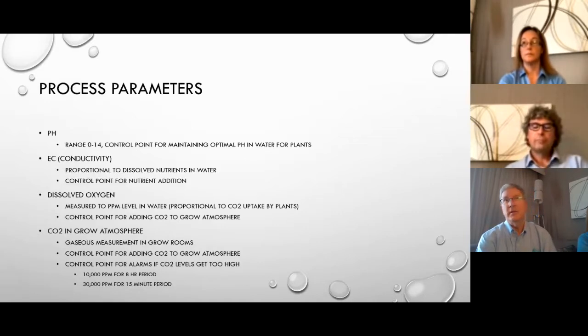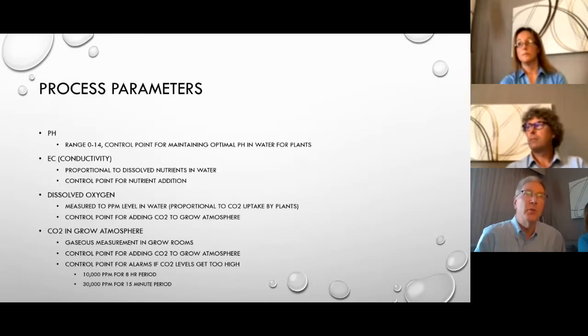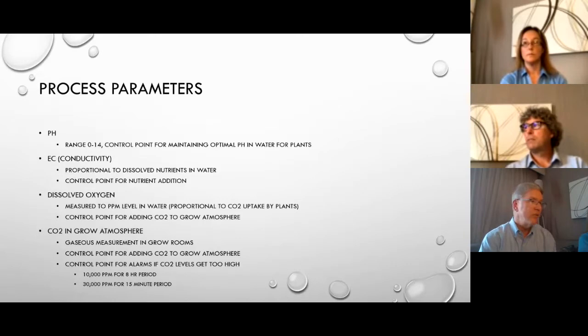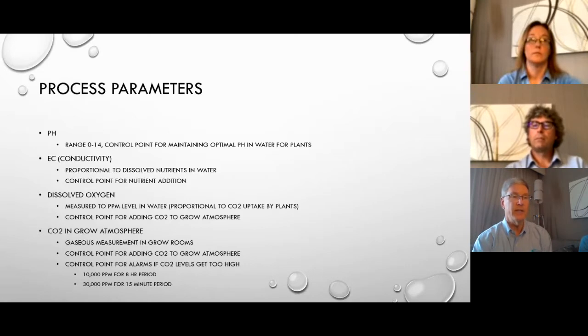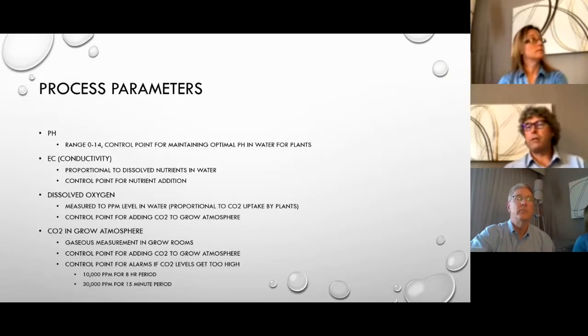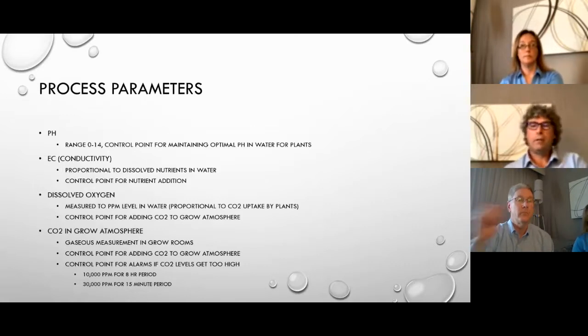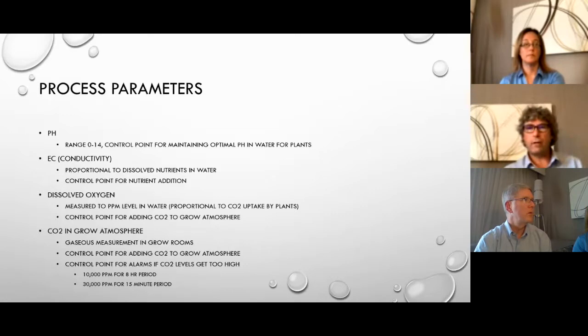Timing of that calibration schedule is usually determined by what we call the authority having jurisdiction. In this case, that's usually the grower themselves, depending on how confident they are in the instruments they have. But usually it's anywhere from every week, every month, to every quarter, depending on the actual instrument being used. Yeah, and it's crucial to spot check the calibration of most of these sensors biannually or on some kind of maintenance schedule to confirm they're accurate. Because if you're controlling to a sensed value and it's not accurate, you have no way of knowing if your product is coming out the way it should be.